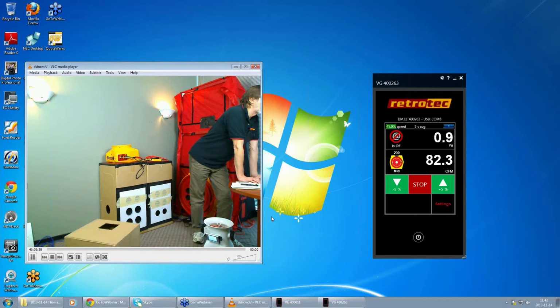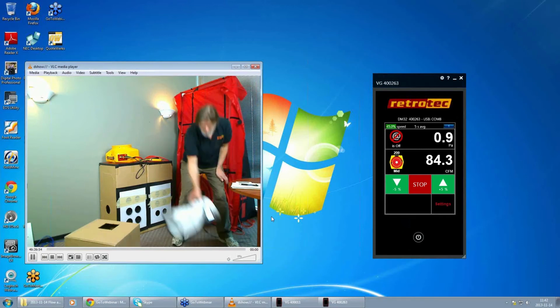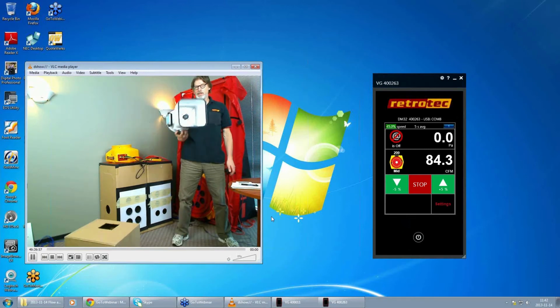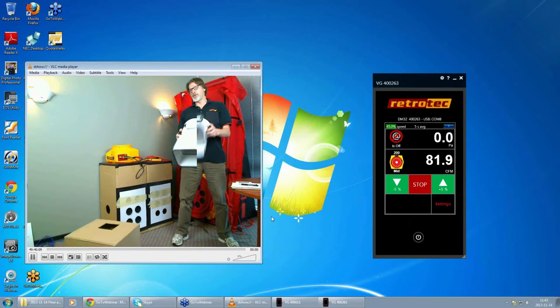I think I've handled all the questions here. So somebody asked, can the Flow Hood Flow Finder be used to measure the extract fan ventilation rates for standard extract as well as mechanical ventilation heat recovery systems? So this little device here will measure flow rates balanced to zero pressure balanced flows up to 330 CFM, unbalanced to 850 CFM. We currently have a hood that will fit on a 2-foot by 2-foot register. We plan on making bigger hoods than that, so you could do commercial or residential, and it goes down to 3 or 4 or 5 CFM.